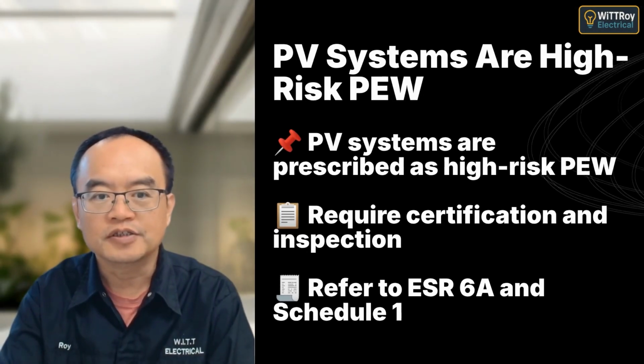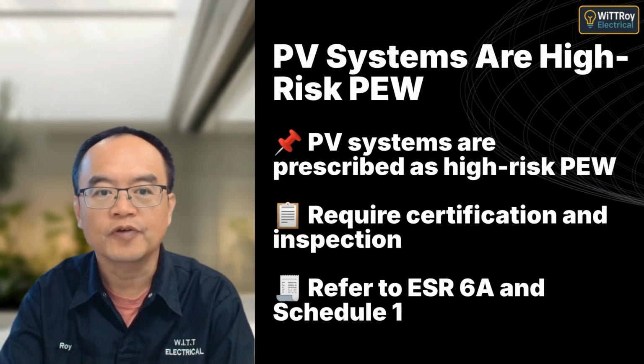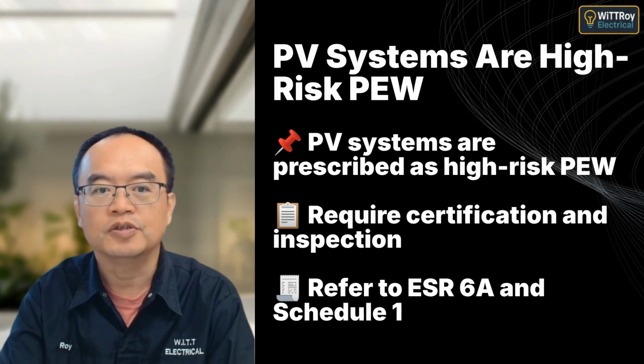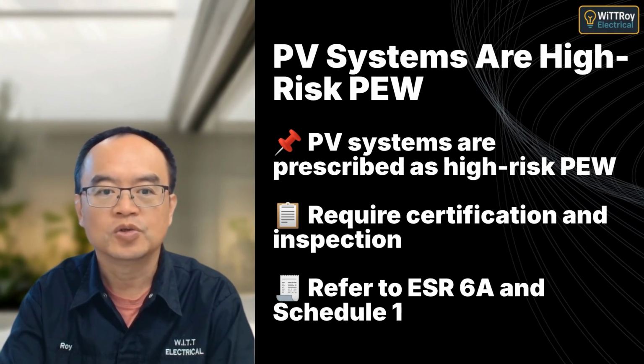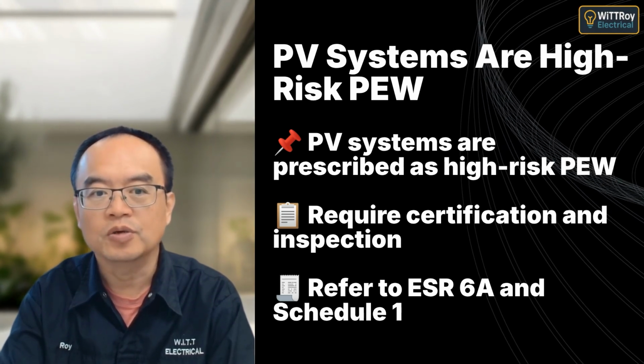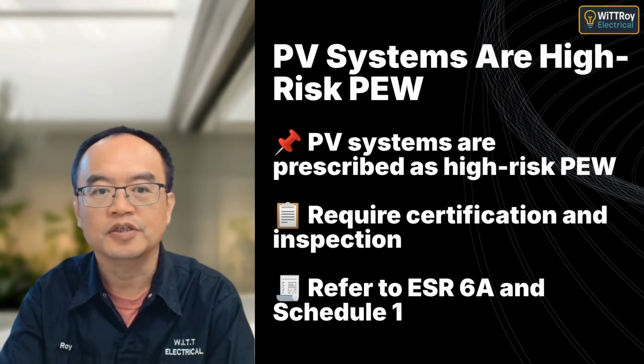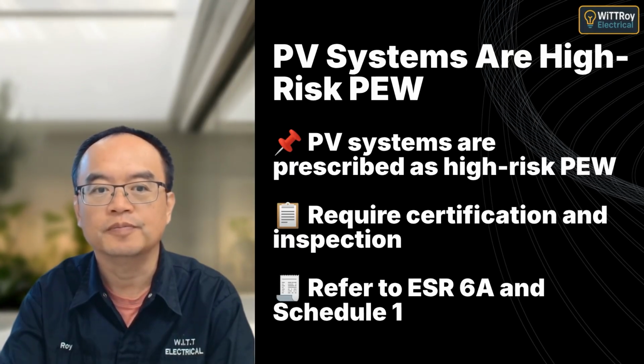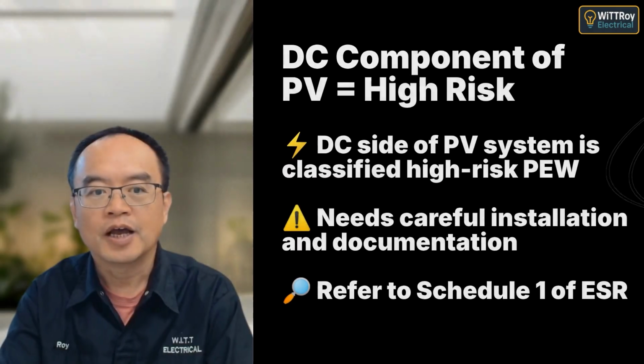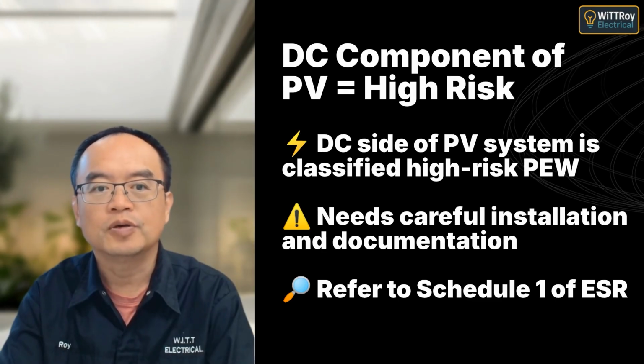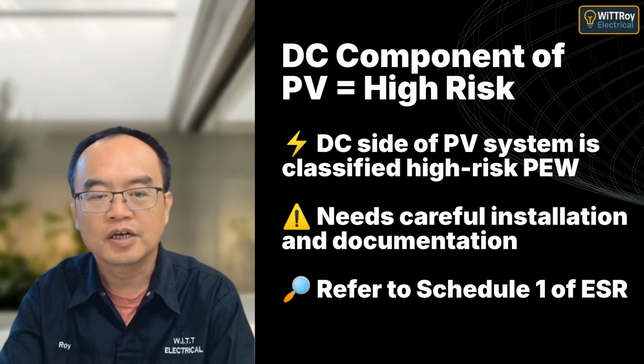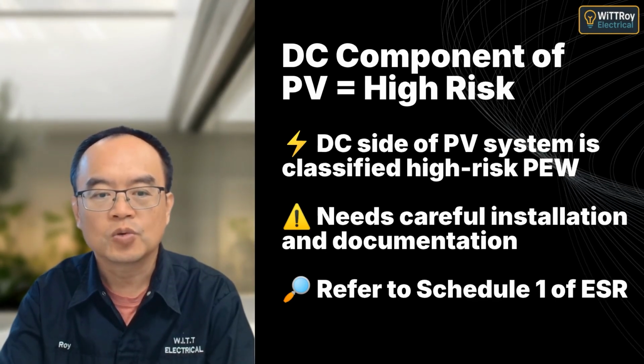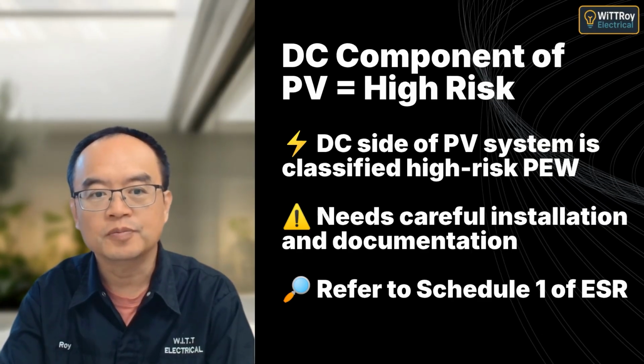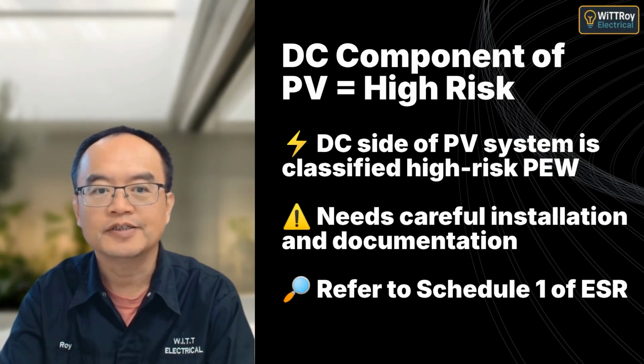According to ESR 6A and Schedule 1, any photovoltaic PV system installed in an installation is prescribed as high-risk prescribed electrical work. This means it must be certified and inspected, no exceptions. Even the low-voltage DC component of a photovoltaic system is considered high-risk PEW under Schedule 1. This means installers and inspectors must treat it with the same seriousness as the AC side.